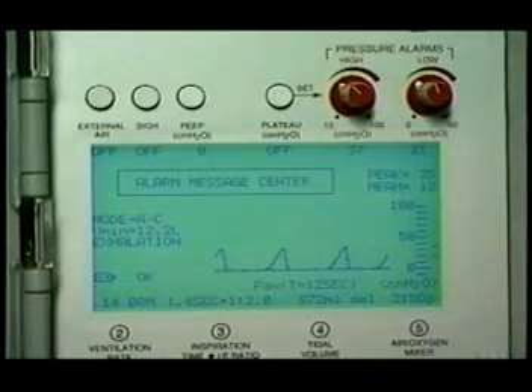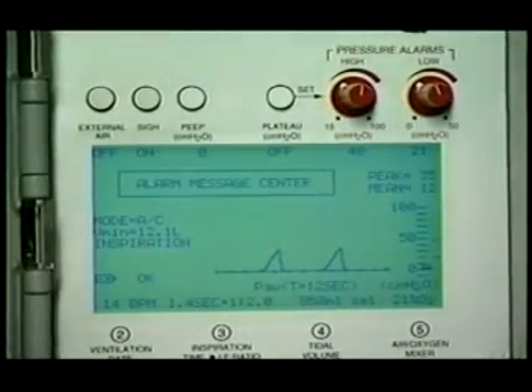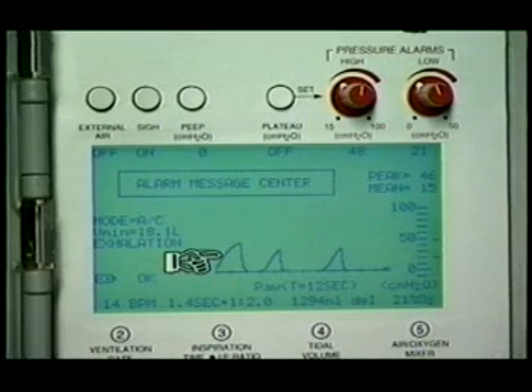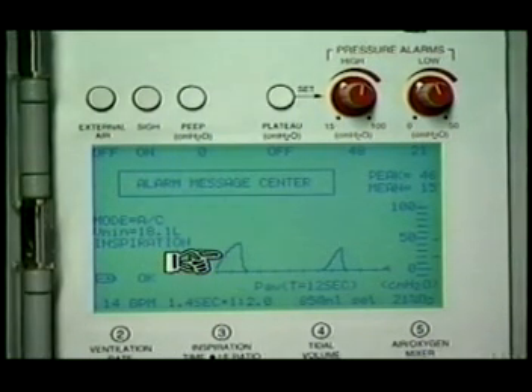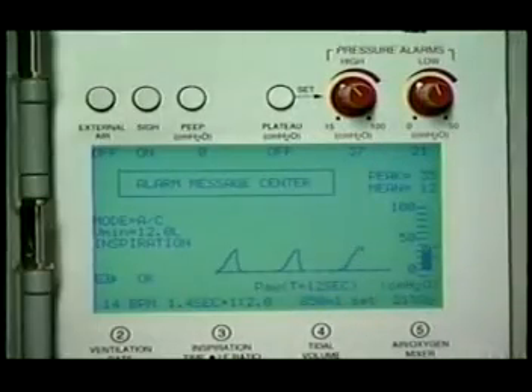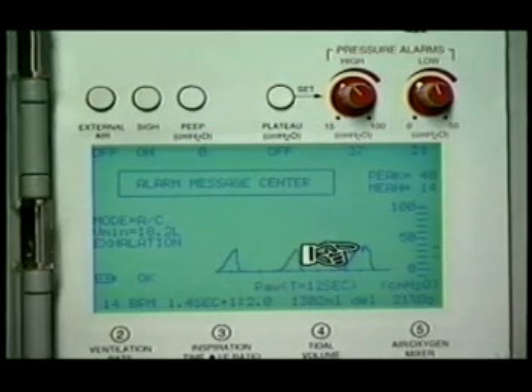If we want to use sigh, press its push button to on. A sigh breath is 150% longer than the inspiration time setting. It is delivered once every 7 minutes or 100 breaths, whichever occurs first. As soon as you press the sigh push button to on, the first breath delivered will be a sigh. A sigh breath cannot last for more than 3 seconds. It appears on the display as a longer breath with higher amplitude and is distinguishable from a normal breath. If a sigh breath exceeds the high pressure alarm set point, its peak will be clipped for safety purposes.